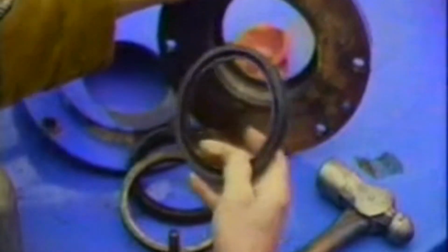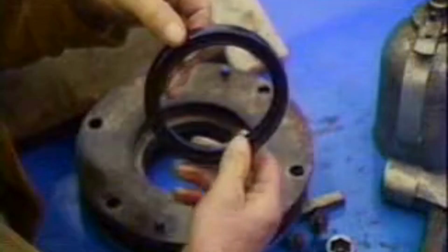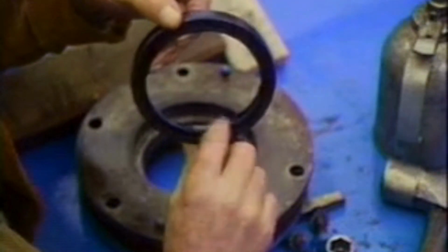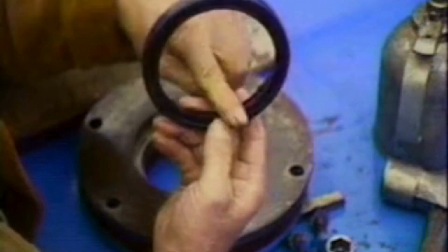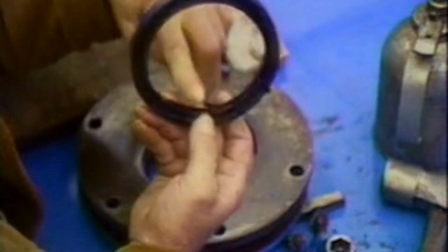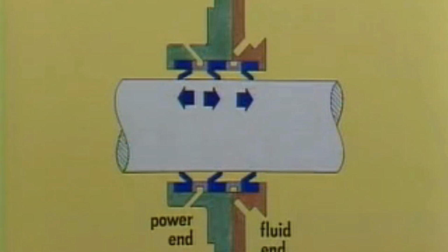You should have 3 wiper rings and 2 metal lantern rings, as well as the diaphragm housing and diaphragm cover. Save the lantern rings unless they're broken. If the old lantern rings have some nicks or burrs, you'll want to clean them up. You'll also need to clean the pony rod. When replacing the rings, it's very important that you point the sealing inner lip of each ring in the right direction. The side with the groove is the side with the lip.